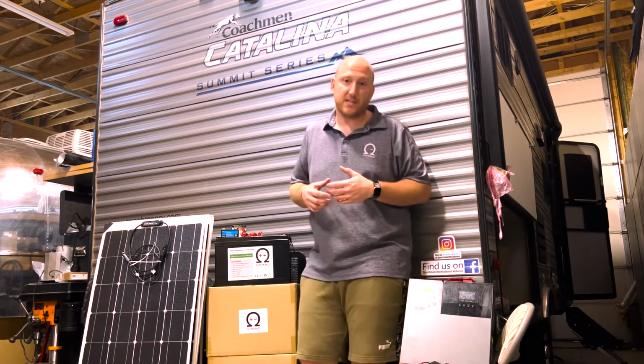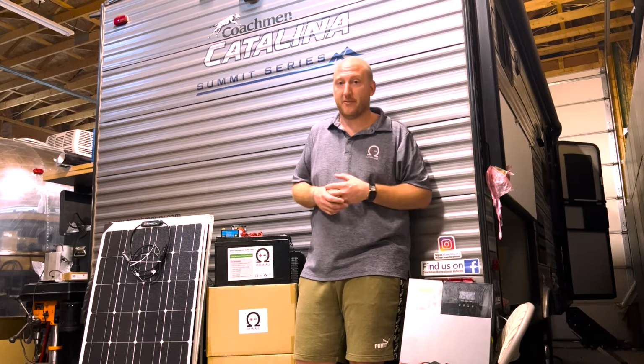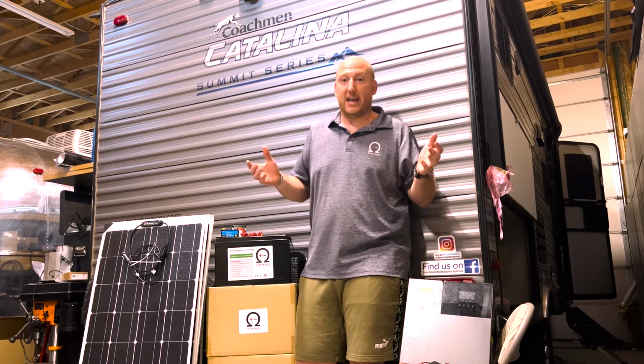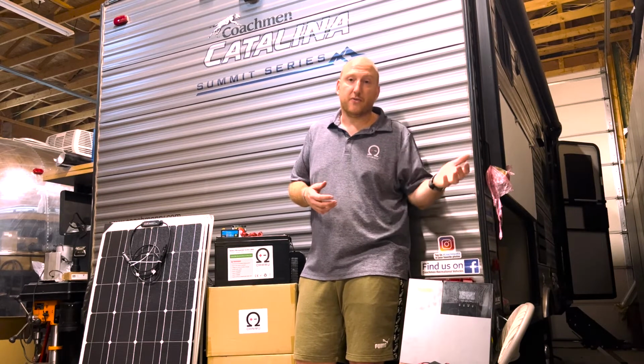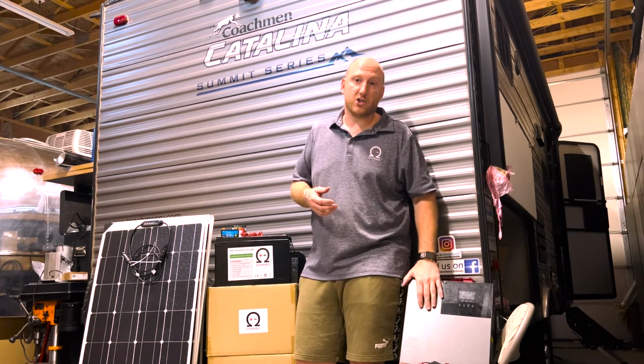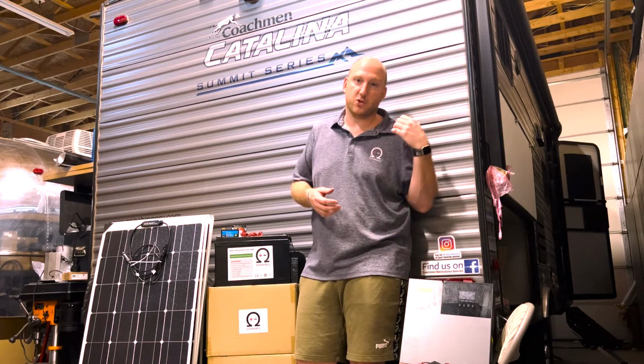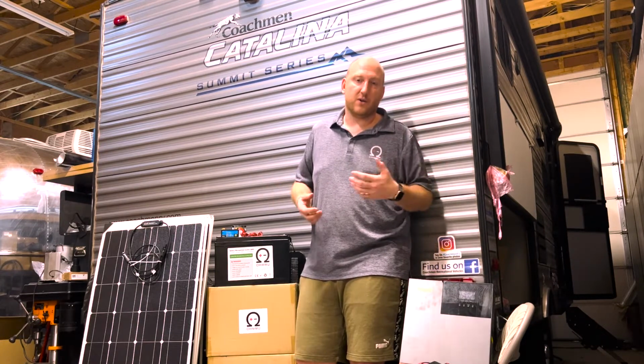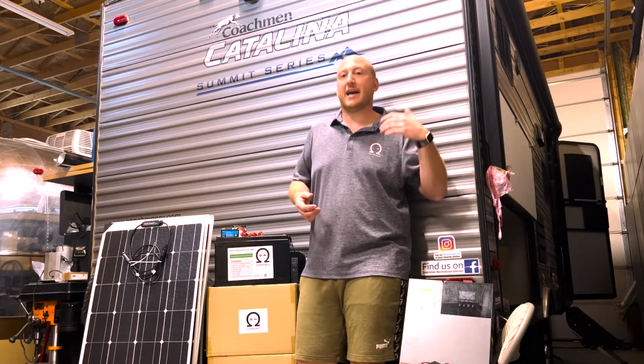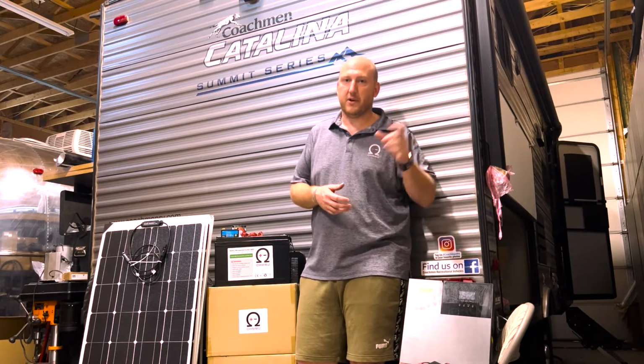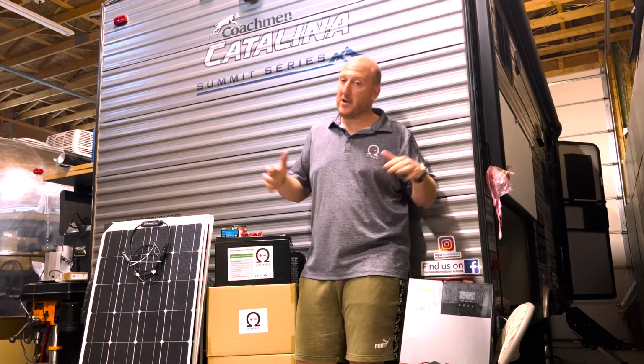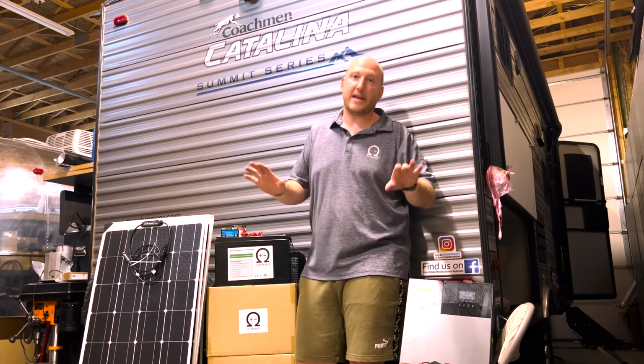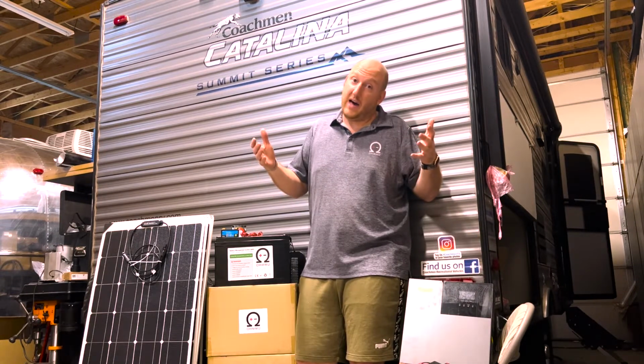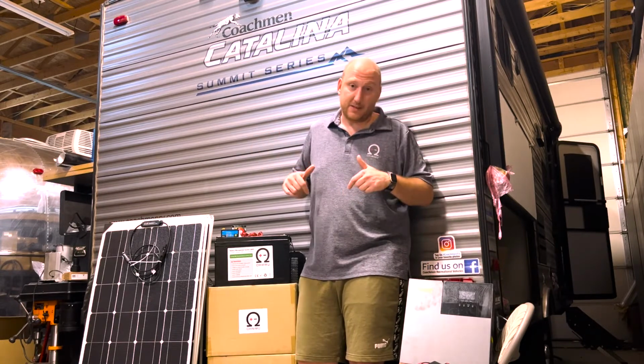If you only have space for 2 batteries, maybe go with a 24 volt system. If you don't have the means to do a 48 volt system for your inverter charger and already have stuff set up in the trailer for 12 volts, go ahead with 12 volts - it's fine, it just won't be quite as efficient, so you lose a little runtime. But when you're starting fresh and designing your system from the ground up, higher voltage is better. That's why in this system we're going 48 volts.